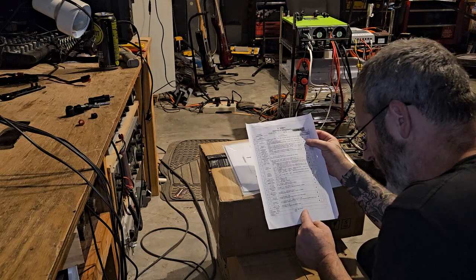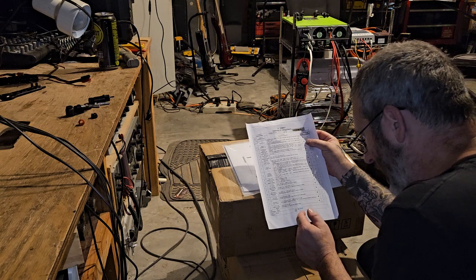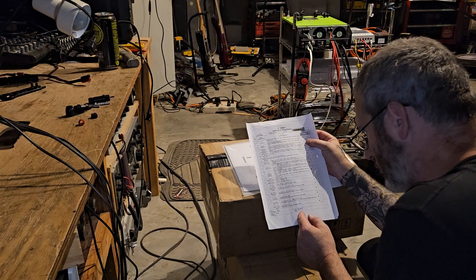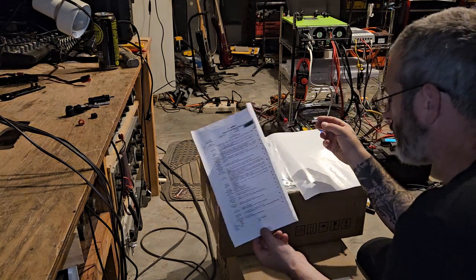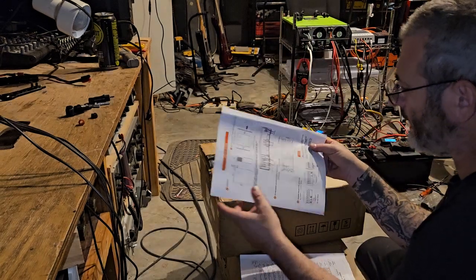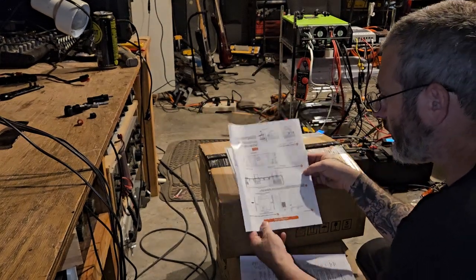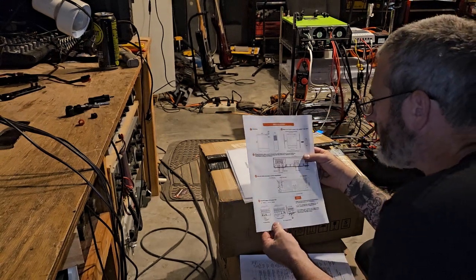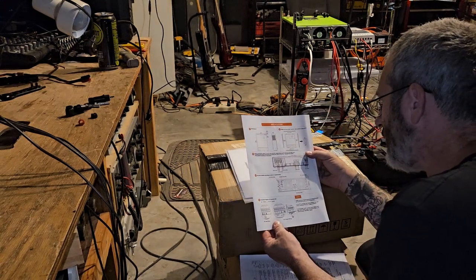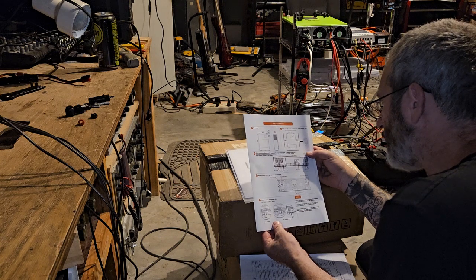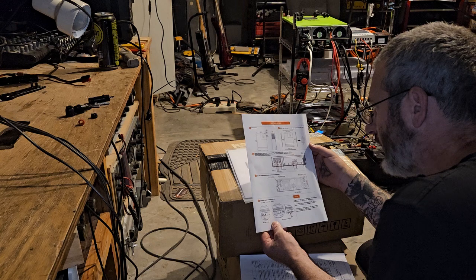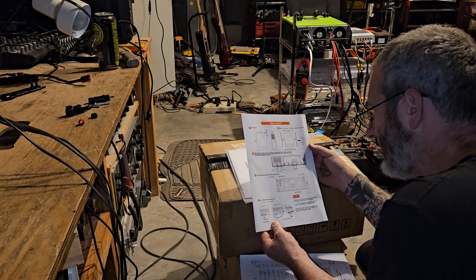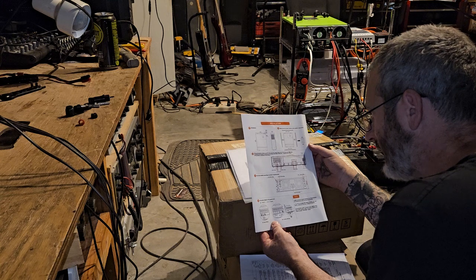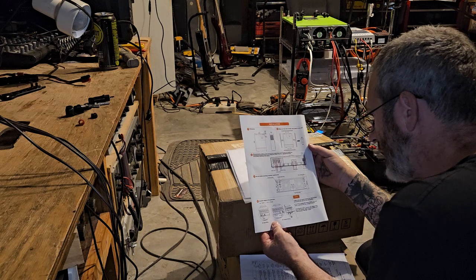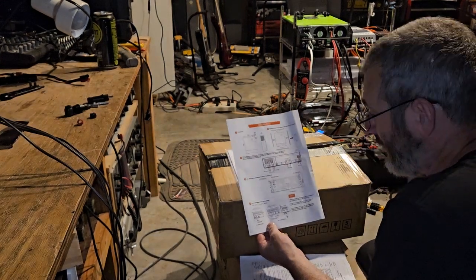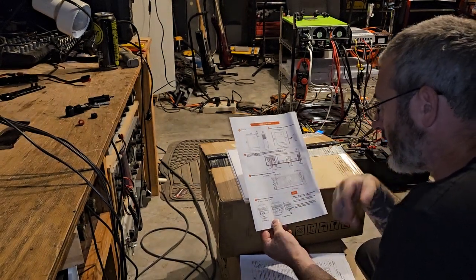And then you have a stamp here, QA. Passed on 8/23/21. And the guy bought this in 2022. So they give you this little piece here that shows the inverter, gives you the dimensions, make sure solar inverter main power is turned off, wiring instructions. And these are really strange because they have the AC wiring in, and they do not give you a ground wire on the AC out, which I have not figured out why that is.